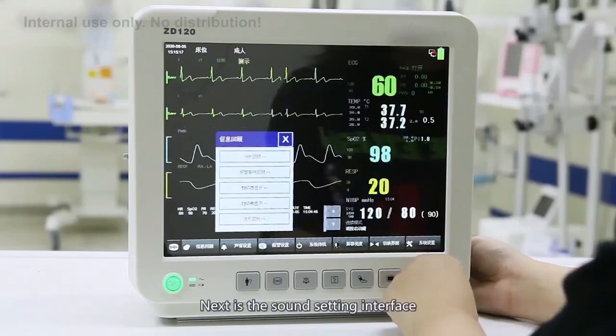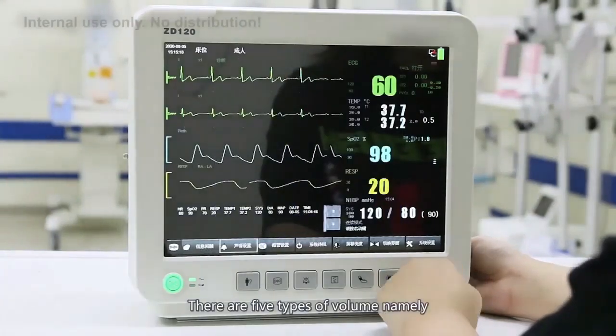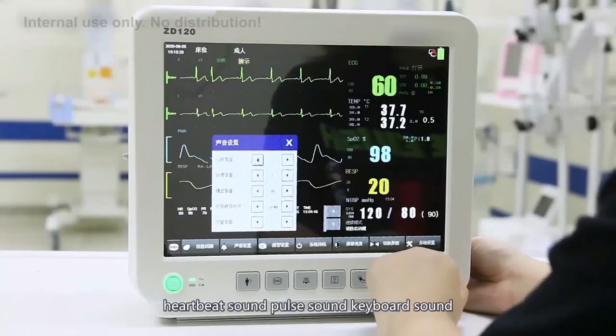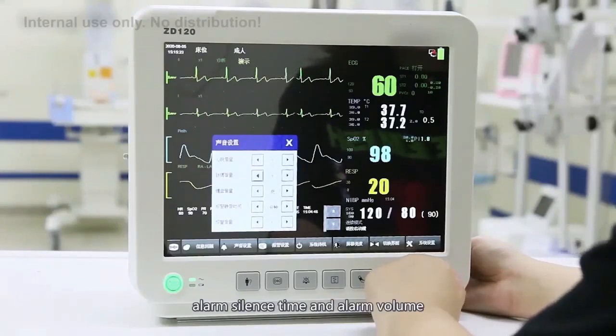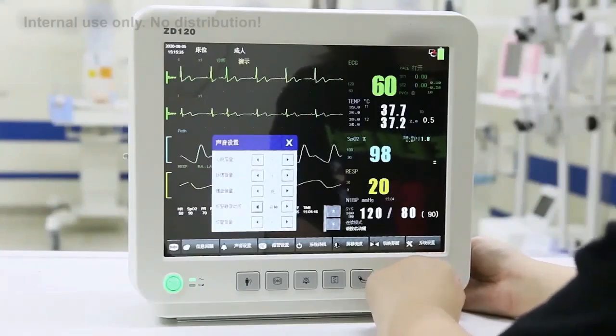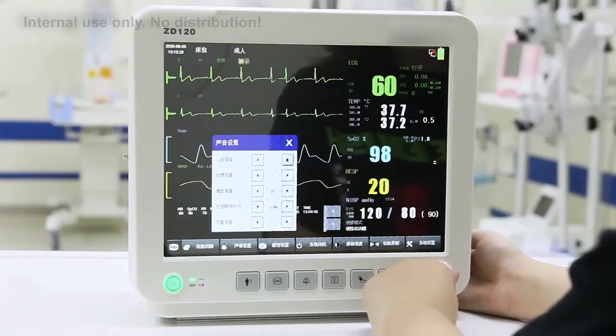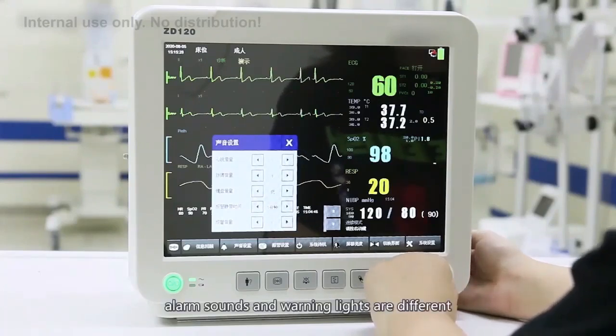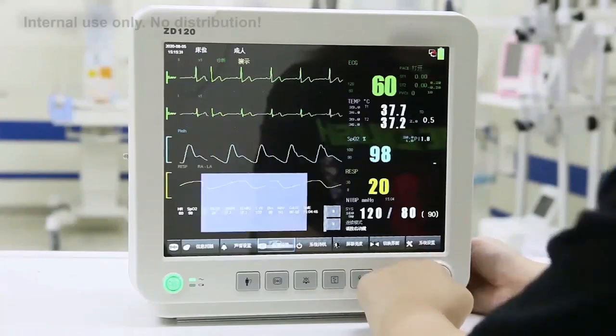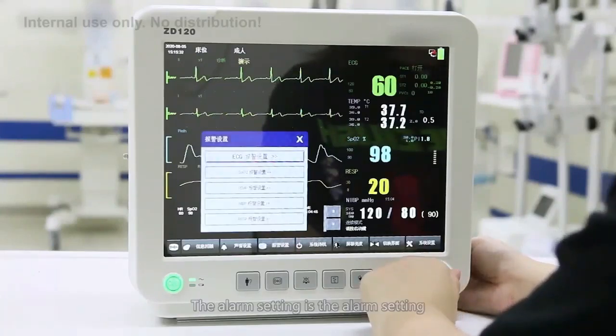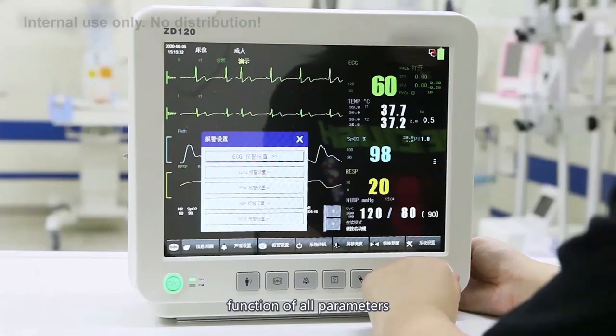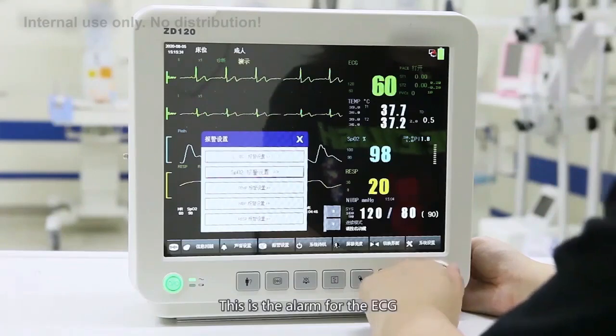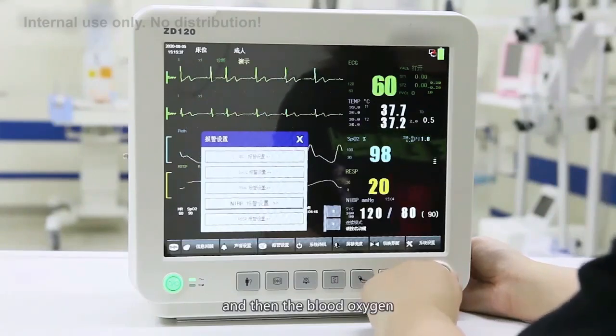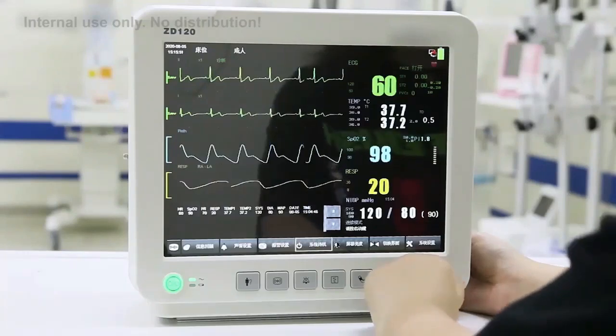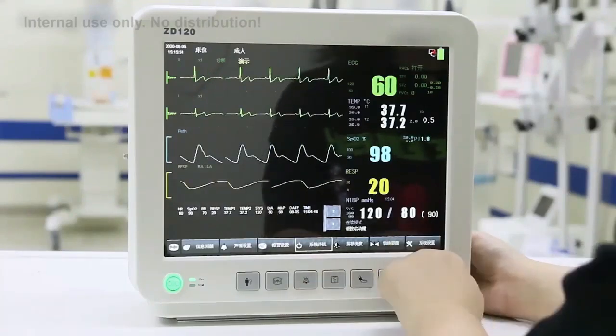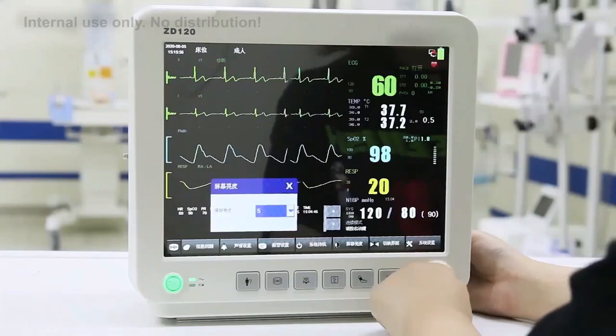Next is the sound setting interface. There are 5 types of volume, namely heartbeat sound, pulse sound, keyboard sound, alarm silence time, and alarm volume. Every sound can be adjusted. Different levels of alarms have different alarm sounds and warning lights. There is also alarm setting. The alarm setting is the alarm setting function of all parameters. This is the alarm for the ECG, and then the blood oxygen, blood temperature, blood pressure, and the respiratory rate alarm settings. This is the system standby mode.